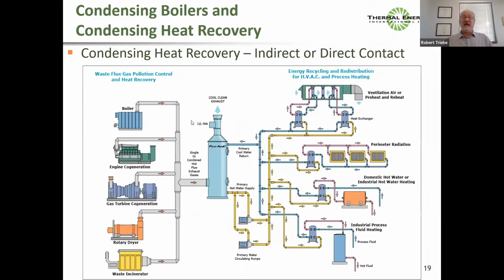All right. And then I like to show this slide as well, because when you're doing this heat recovery, this is almost application, which is the next subject, but I wasn't sure where to slide this one in. Something else to consider is very often the feed water economizer, it's always one boiler, one feed water economizer, and the feed water economizer addresses only the heat sinks related to that specific boiler.